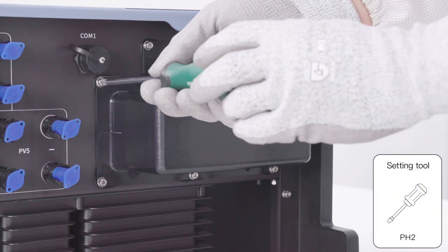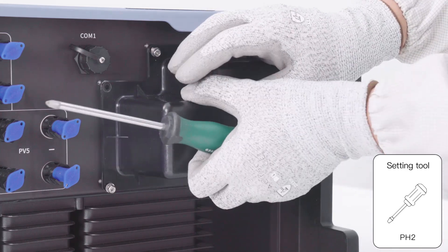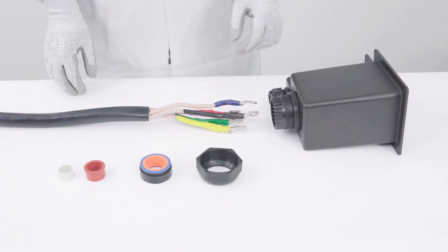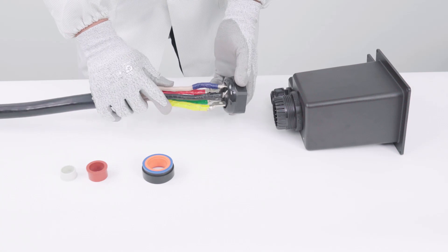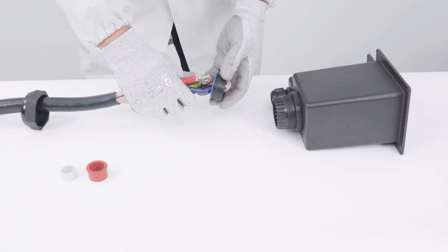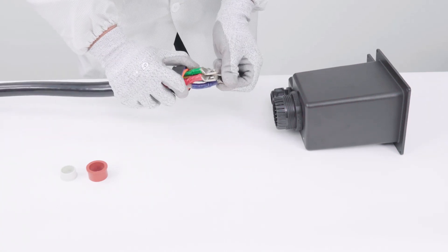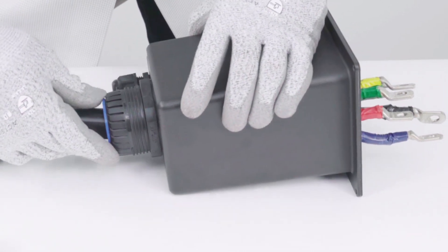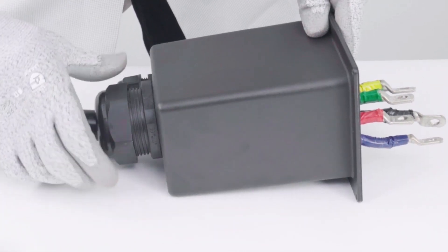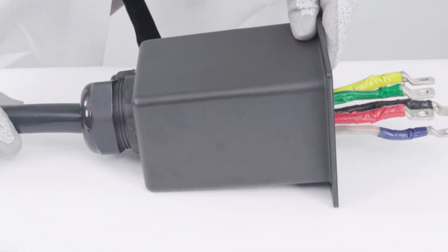Remove the AC/COM terminal cover from the inverter. Unscrew the swivel nut from the cable gland for the AC connection at the connector cap. Thread the swivel nut over the AC cable. Route the AC cable into the inverter through the cable gland.